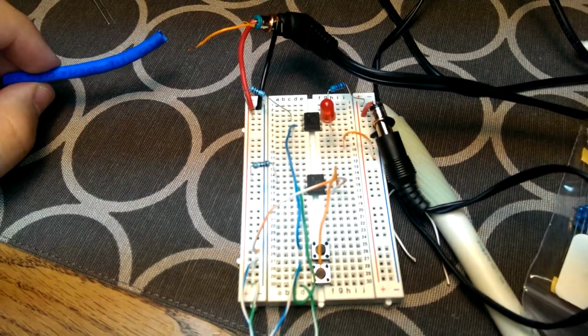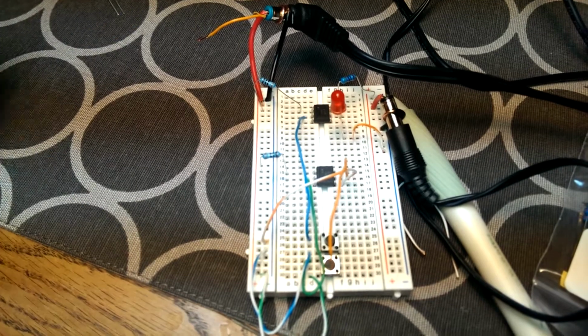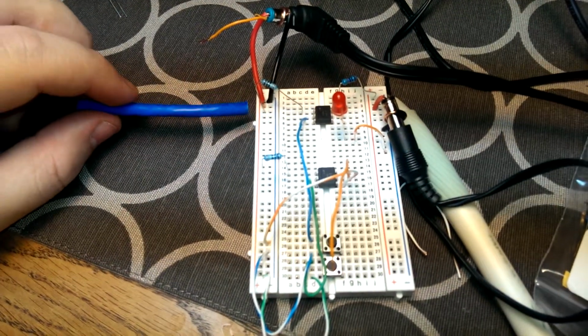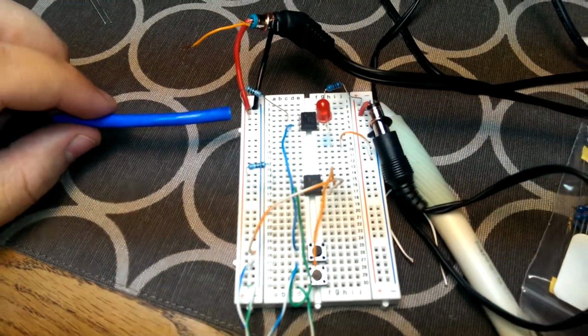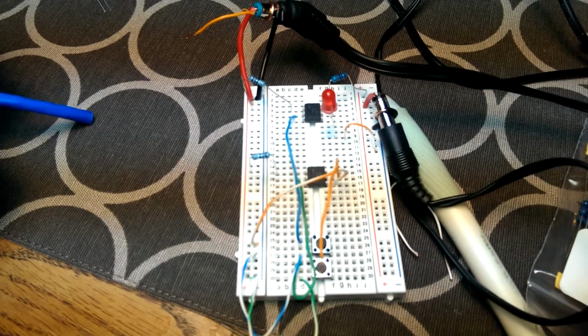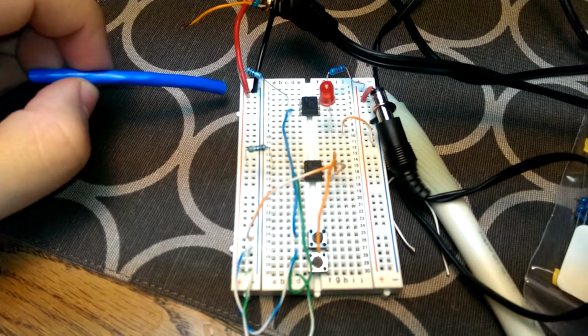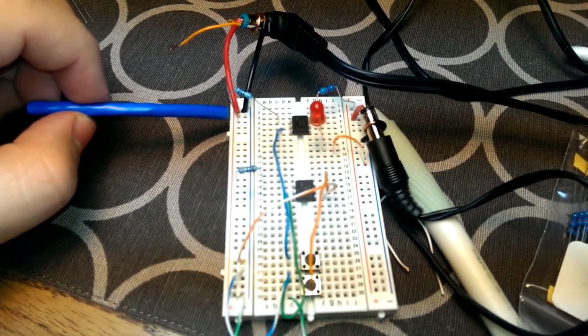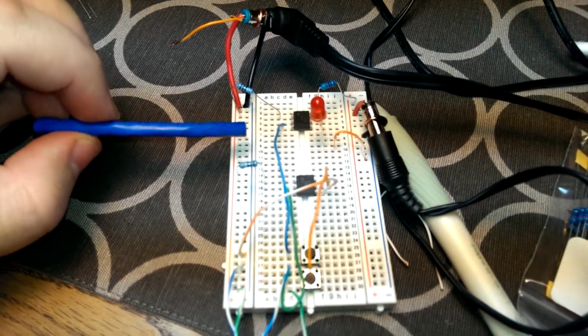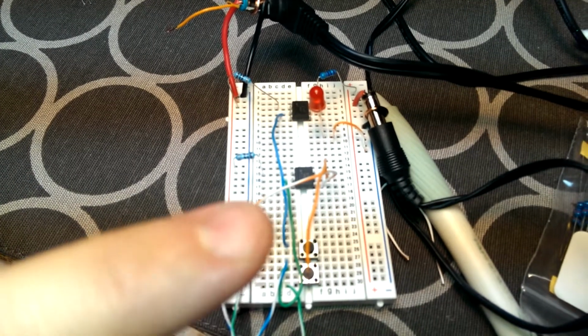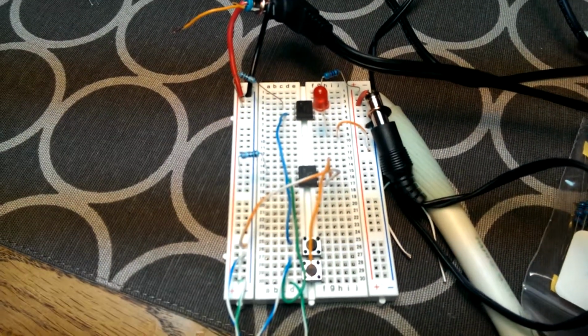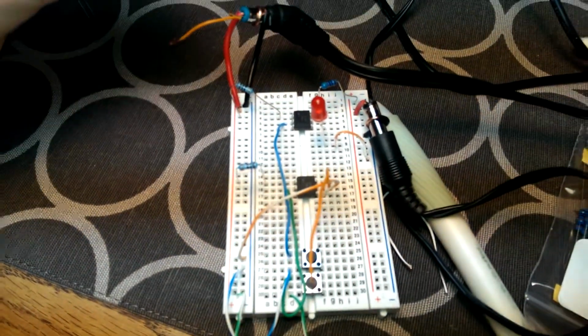And what that will do is tell my channel back at the studio to turn on. That's all I'm asking it to do, because the automation will stop everything else when I need to, and all I need is for this thing to turn on and be armed and ready. So, pretending there's another one out on the internet, we'll call it A. The one at the studio is going to be B. So B is going to send me on output 1 ground, which I'm simulating with this switch down here, switch number 1.